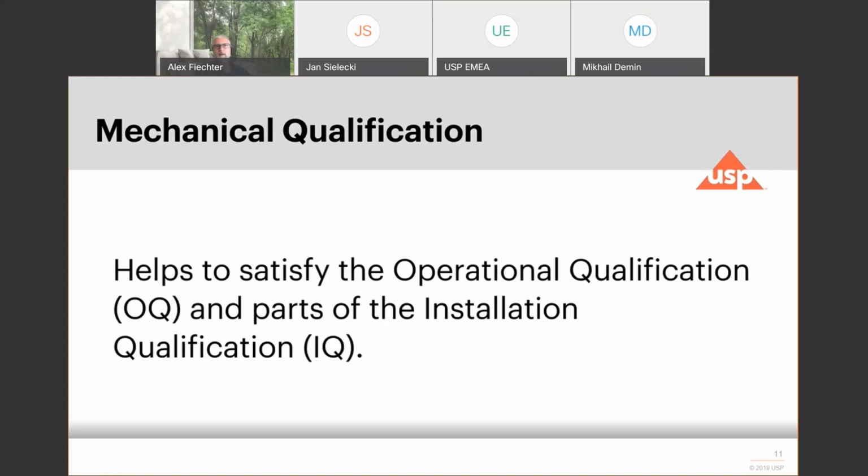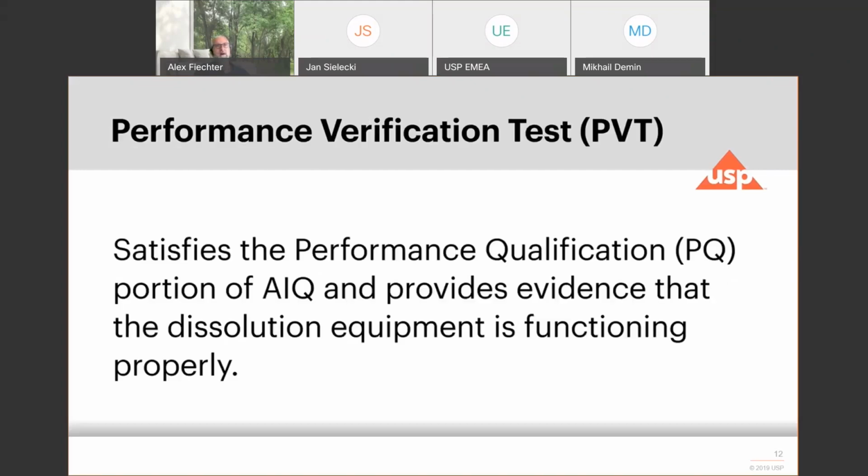There are customers who do the PVT on a yearly basis, others on a 6-monthly basis. We always recommend that how many times you have the equipment in use and how many batches you are releasing should qualify the number of qualifications that you do. If you have a dissolution tester that releases batches on a regular basis, it may suffice to do this on a yearly basis.